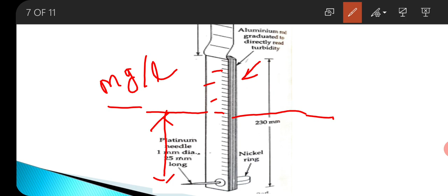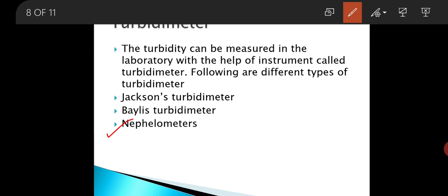Then the next one is the turbidimeter. The turbidimeter is generally used to measure the turbidity of water samples in laboratories. There are different types of turbidimeter: Jackson turbidimeter, Baylis turbidimeter, and nephelometer. The nephelometer is a widely used turbidimeter, and it is based on the principle of scattered light. In this turbidimeter, the intensity of scattered light serves as a measure of turbidity.